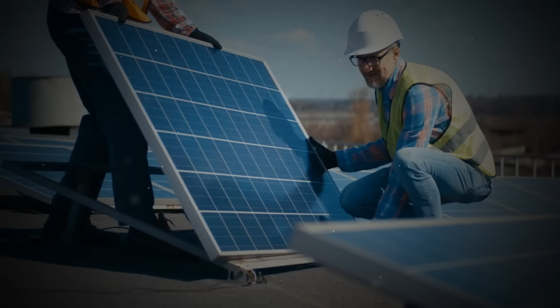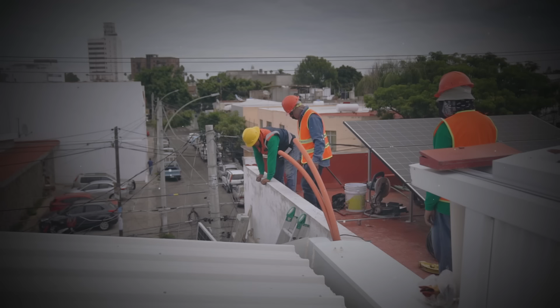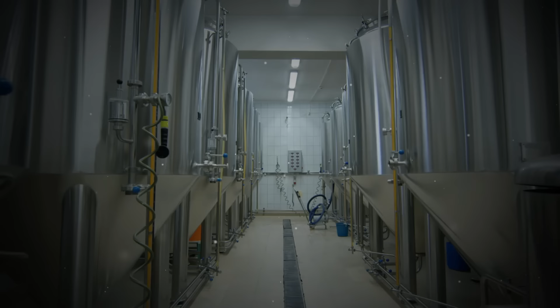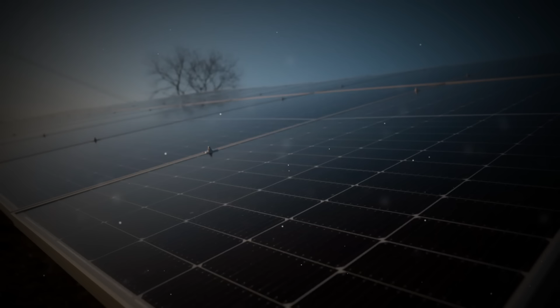Live panel work demanded insulated gloves, face shields, flame-resistant clothing, and careful sequencing to prevent arcing or inadvertent shorts. Thomas carried these responsibilities conscientiously, but was aware that client pressure could override best practices. Official risk assessments were in place, and the client had signed a waiver allowing live work on a single energized panel, citing the need to maintain refrigeration uptime.